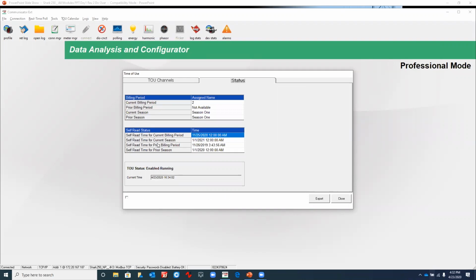Self-read status typically means that the meter does what we call an automatic reset. If you set the frequency of how you want it to reset, it will do an automatic reset. For instance, if you wanted to reset once a month at midnight, at the end of the month, to bill a customer, you would set this up for self-read at the end of the month. And that is tied to a calendar in the system where you would set your date and time for that period, and the meter would execute the reset.